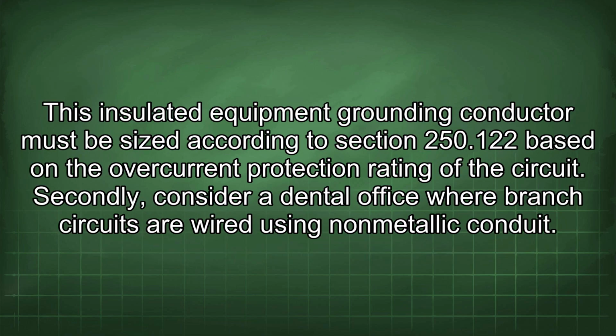This insulated equipment grounding conductor must be sized according to section 250.122 based on the overcurrent protection rating of the circuit. Secondly, consider a dental office where branch circuits are wired using non-metallic conduit.